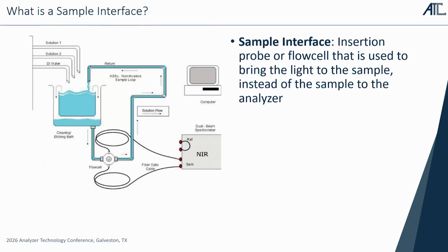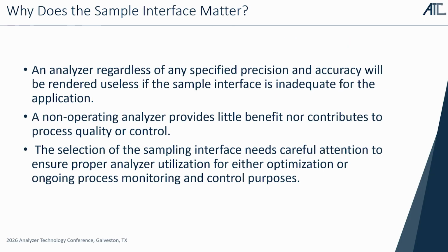Okay, so what is the sample interface? The sample interface is usually that probe that we have either in a bypass line or directly in situ that's sitting there, and that's where the light and the sample are interacting. And it really doesn't matter how good of an analyzer you buy. If that probe or that sample conditioning system fails, if it plugs up, if it fouls, your analyzer's no good, right? If somebody comes through and they drive a forklift through your fiber cable conduit and they break the connection, that $1 million analyzer or that $30,000 analyzer isn't gonna give you any information. You're gonna be running blind, you're gonna be back to grabbing samples.